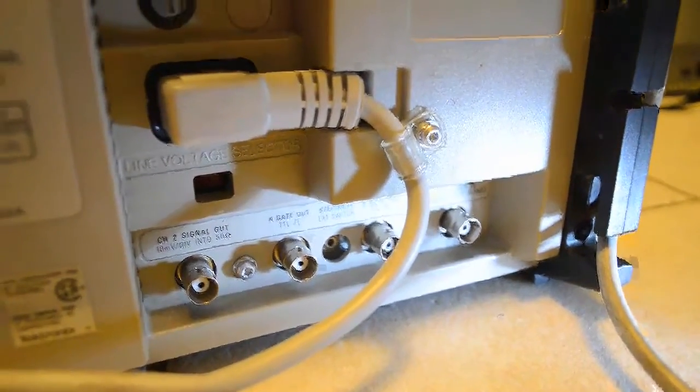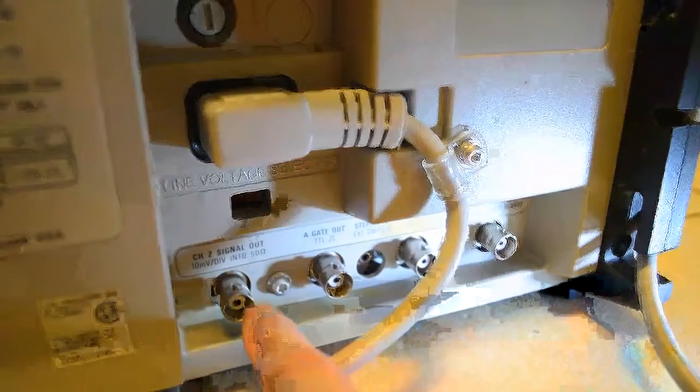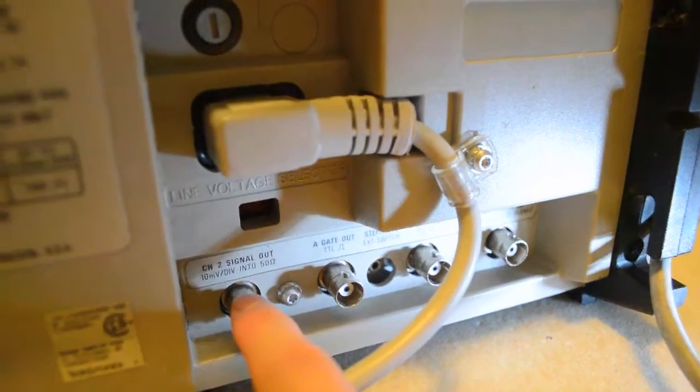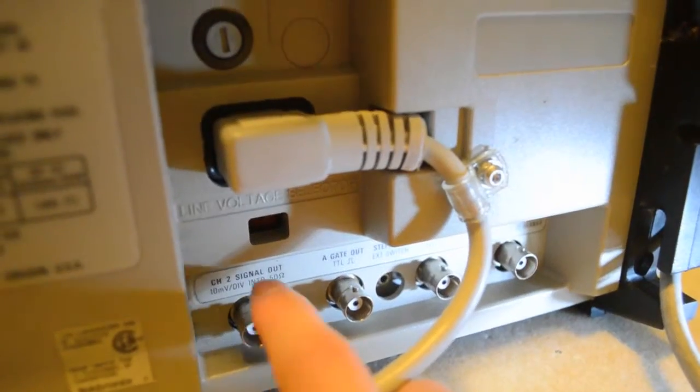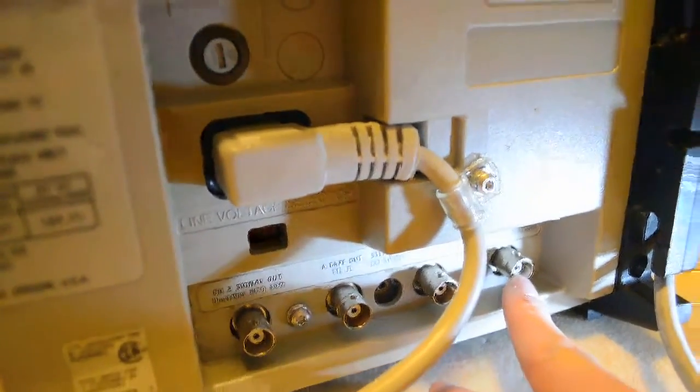Okay, so I'm going to start in the back. This whole unit looks pretty good for having been shipped across the US. We have four BNC jacks in the back, and we have a channel 2 signal out. It's a representation of what you put in the channel 2. Two gate outputs, A and B, and we have our external Z-axis input. And also, we have a free dead spider hanging out there. I'll clean that out in a sec.